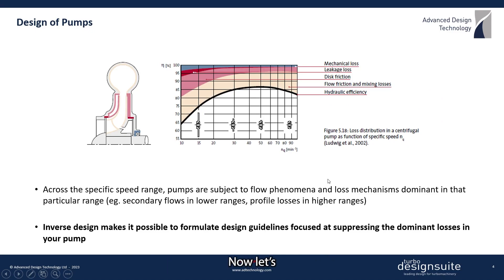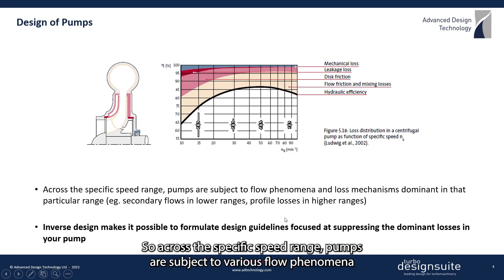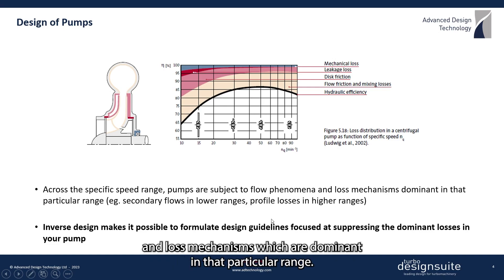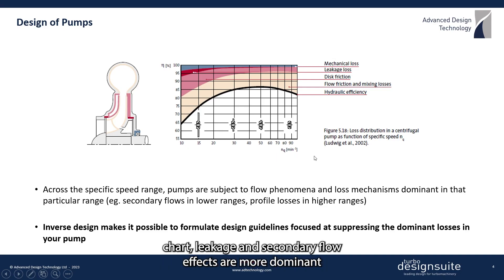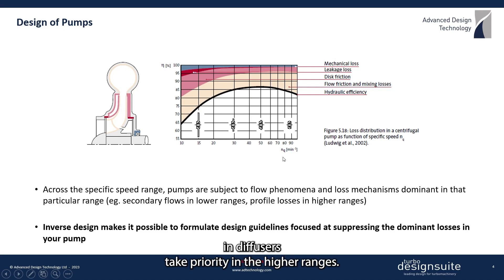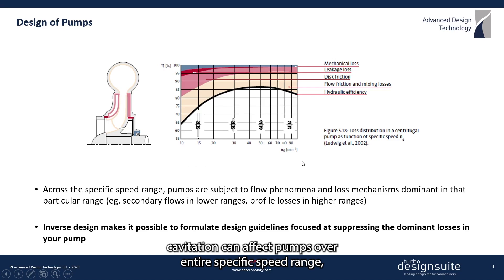Now let's look at the design of pumps in a bit more detail. Across the specific speed range, pumps are subject to various flow phenomena and loss mechanisms which are dominant in that particular range. As you can see in this specific speed chart, leakage and secondary flow effects are more dominant in the lower ranges, whereas profile losses and corner separation in diffusers take priority in the higher ranges. A phenomenon such as cavitation can affect pumps over the entire specific speed range, and this is something that must be dealt with on a case-by-case basis.